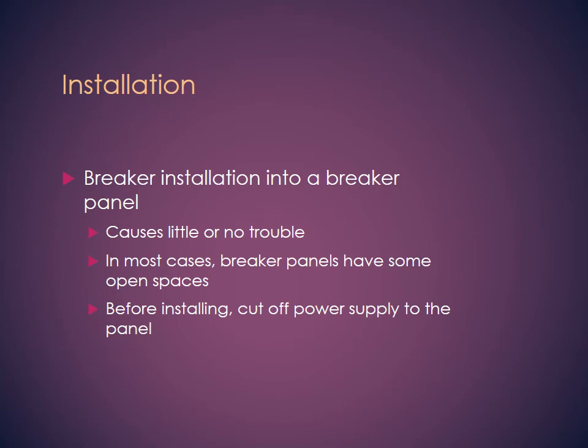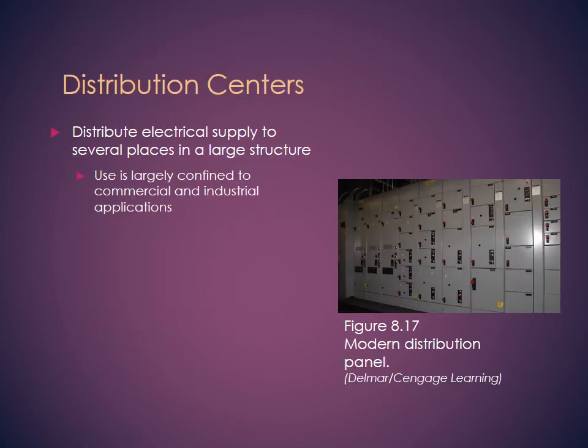Before installing anything, this is important. Before changing a breaker or installing a new breaker, you have to cut off the main power, and that's why sometimes we have a main connection to the distribution center, which is a combination of all those little disconnect switches put together in a control room, because probably this is operating a big manufacturer or also a big power plant. So you want everything handy so you can go and shut off equipment if you have to, or if there's an alarm in one area.